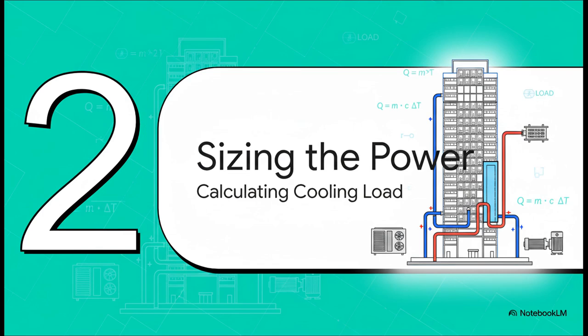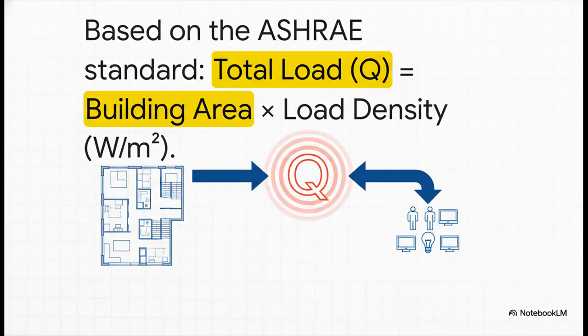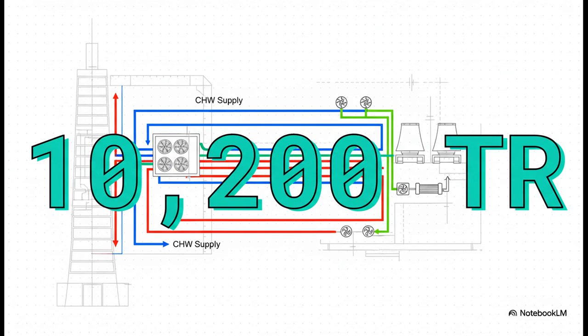All right, so we've established that the pressure is a massive hurdle. Now, let's switch gears and figure out just how much cooling power we even need for a monster of a building like this. We're going to start with the classic ASHRAE formula. You take the total area of the building and you multiply it by the load density. Now, that density factor takes into account all the heat coming off of people, computers, lights, all of it. And for a 120-floor tower, you can bet that number gets big fast. So after we run the numbers for our example building, we land right around 10,200 tons of refrigeration.